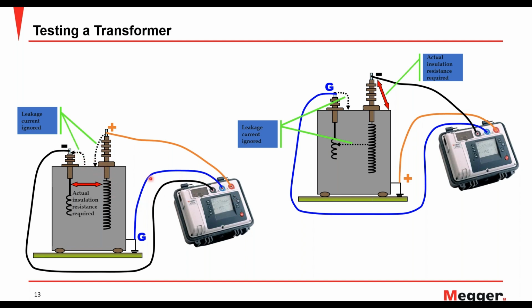Whenever I hook up this guard terminal, anything that this guard terminal reads is subtracted from your actual reading. So any leakage current that is going through your surface is going to actually be subtracted out from the reading, and that's how it will give you an insulation resistance reading. That's what the guard terminal is used for. Anything that you want to guard out of the measurement, you can use the guard terminal. That is the blue terminal.